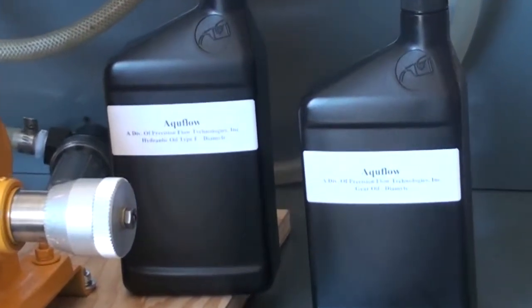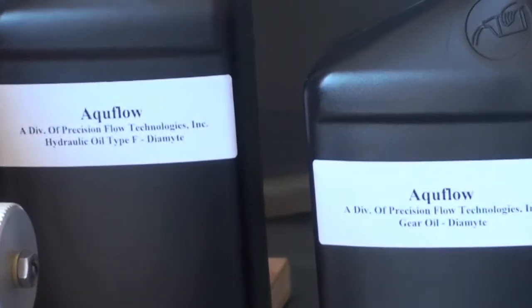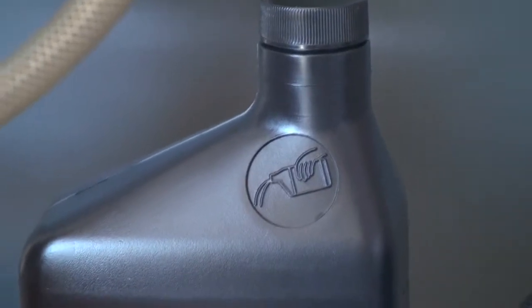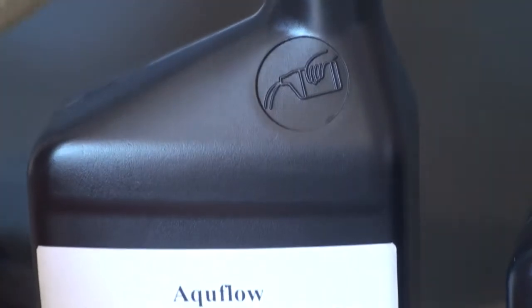Aquflow's Diamyte pump only works using type F hydraulic oil. The reason for using this type of oil is that type F fluids have anti-foaming properties, but more importantly, this fluid does not suspend air bubbles.